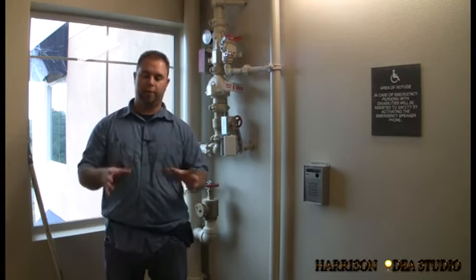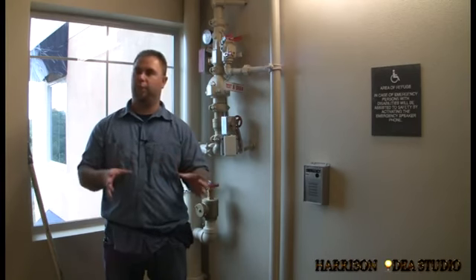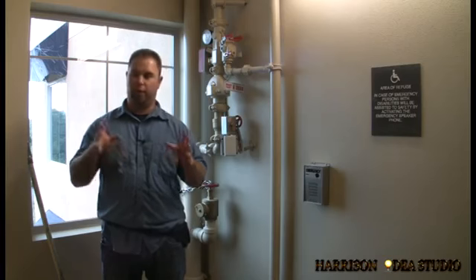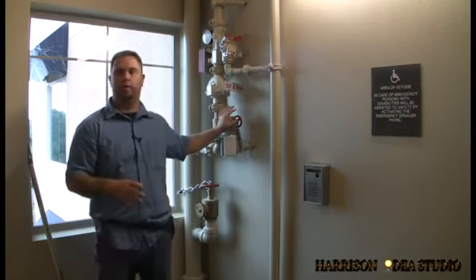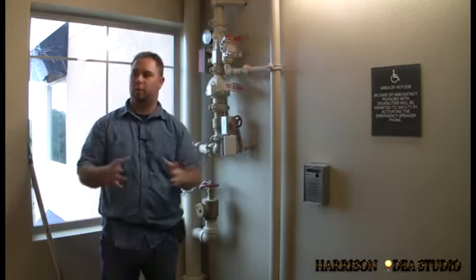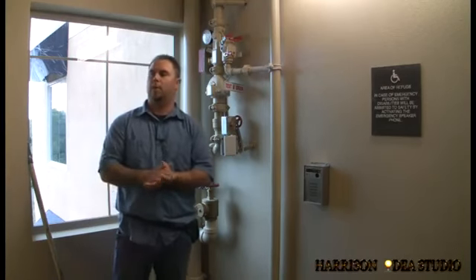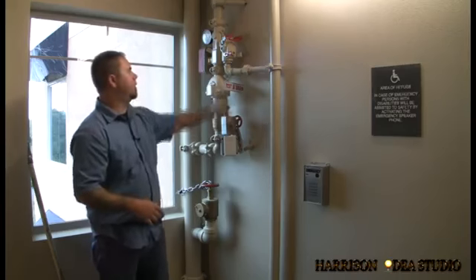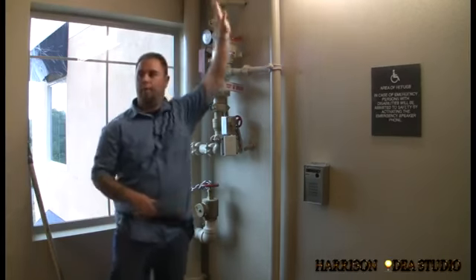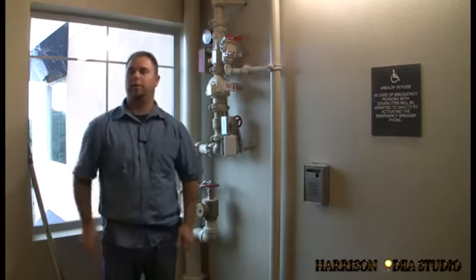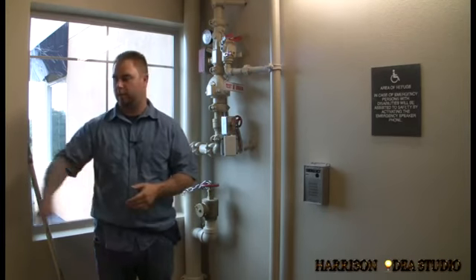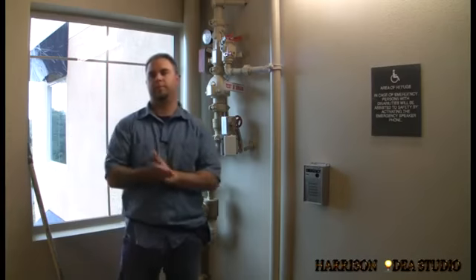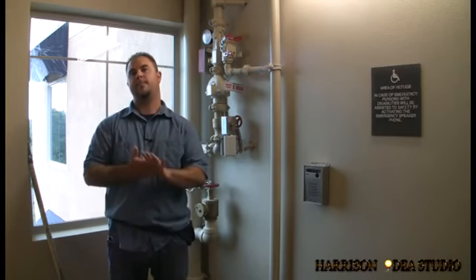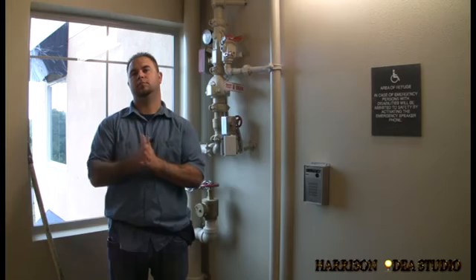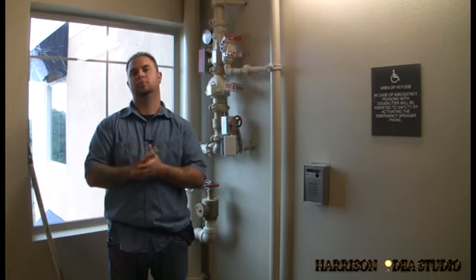Okay. But if maintenance or management figures out that it's an accidental break, at that time, I would recommend shutting off the control valve, opening up the drain, and that'll minimize the water damage in the building. That is the best thing we can do. Yeah, absolutely. Close this valve, open up this drain, open it up all the way, and get all the rest of the water out of the system. Okay. And it'll drain outside and not into your building. Yeah. I imagine at least once this has happened, like somebody taking a ladder through there, walking with a maintenance person, and they bust that off.